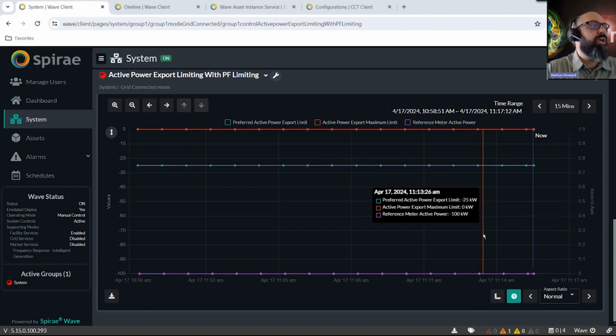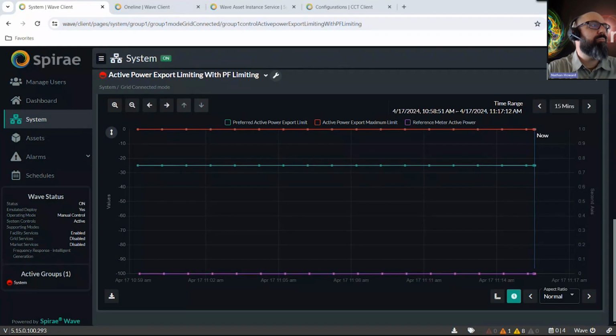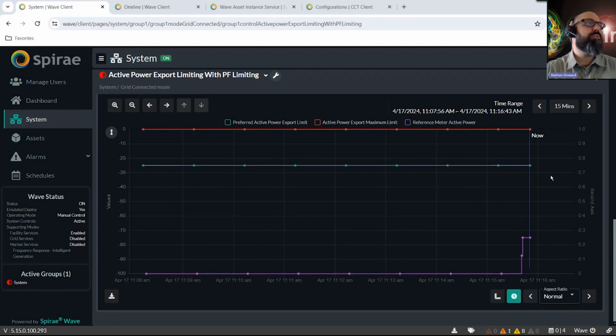So what Don's going to do is use our emulator to ramp up the PV available in the system. So the sun's coming up and our PV system will start producing some power. And as that power becomes available, we'll see that we'll stop using the grid power. We'll use that locally produced energy to the extent possible to meet our energy needs. So we can see that come up, stabilizing there, using that available power. And now as the sun continues to come up, more PV becomes available, our PV production may exceed the current load that we have.